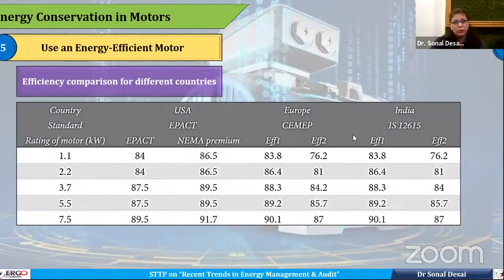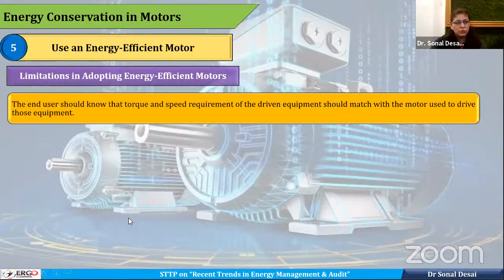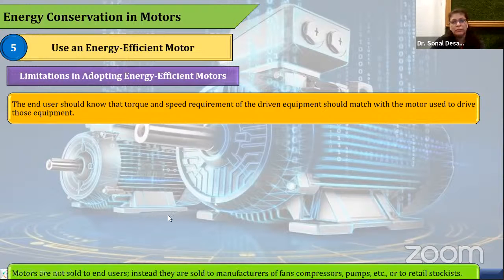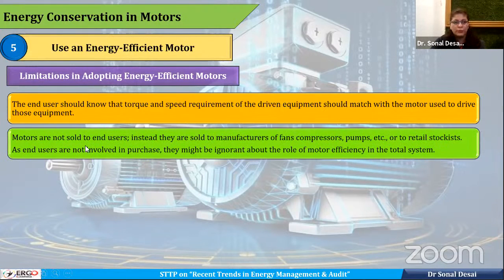Why are people not adopting energy efficient motors? Some hidden stories are shared over here. The end user should always know the torque and speed requirement. When you go to buy the motor, most of the time only these things are known, and efficiency and power consumption are not known. The second and most important reason is that motors are not sold to end users. They are sold to manufacturers of fans. Say, for example, if Crompton is making a fan, then Crompton will buy the motor. You as an individual or me as an individual are not going to buy the motor.